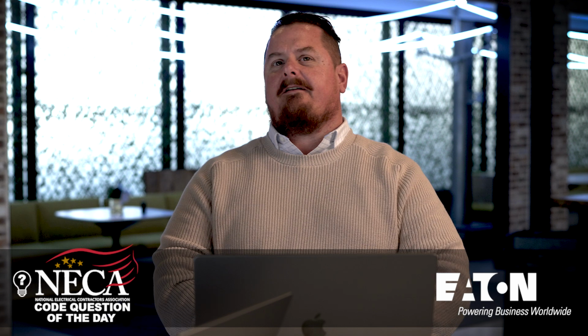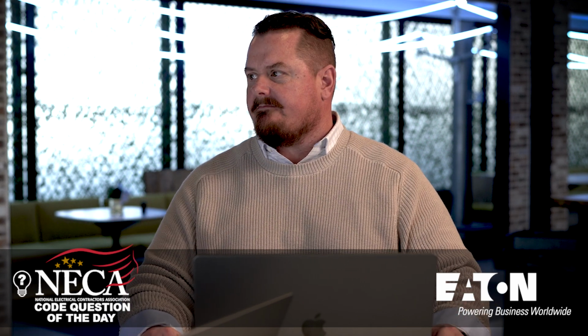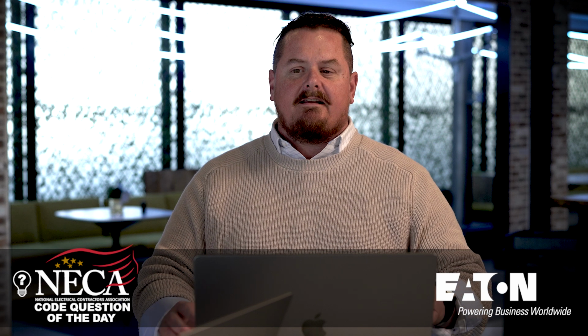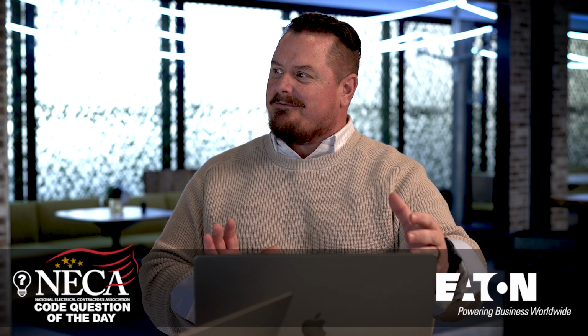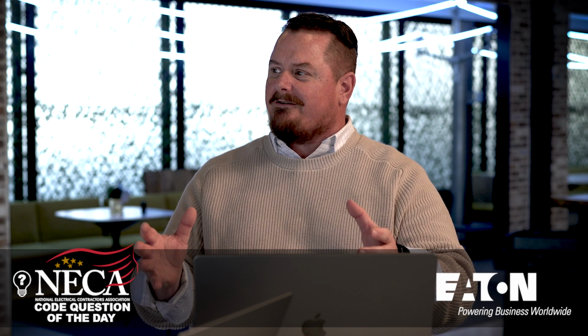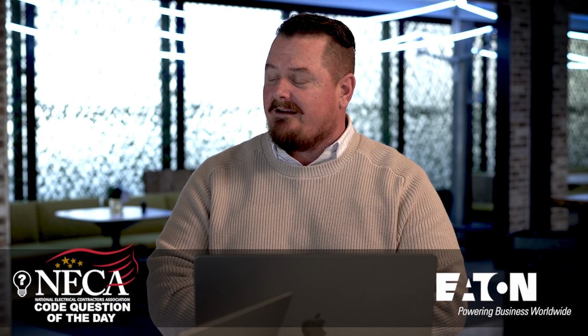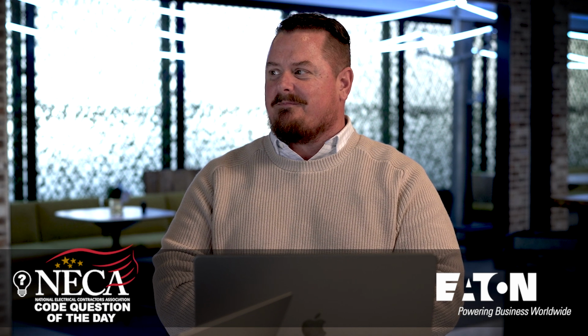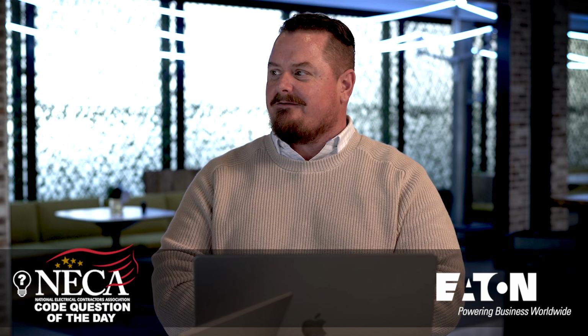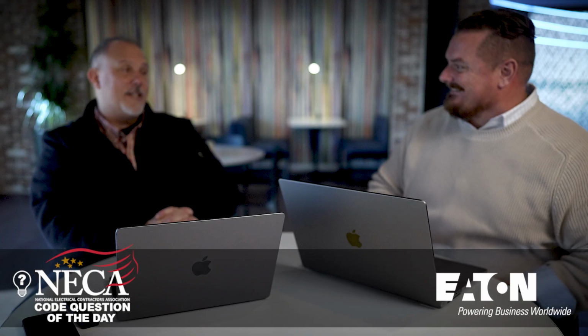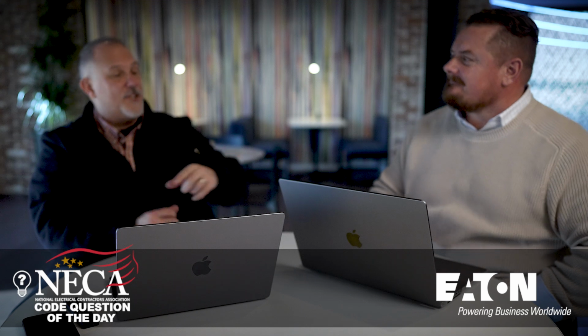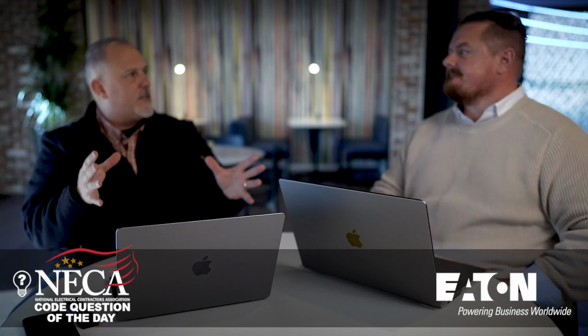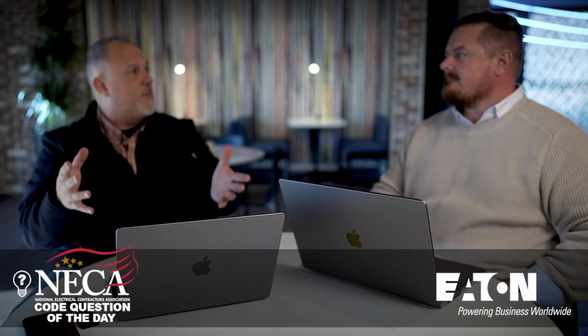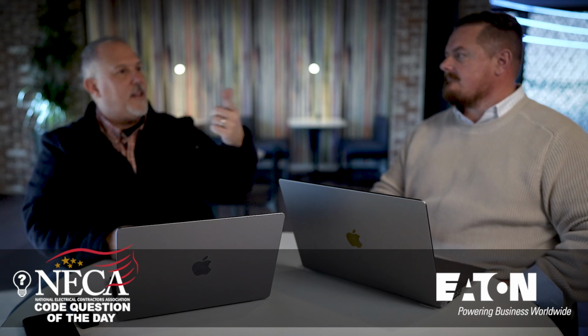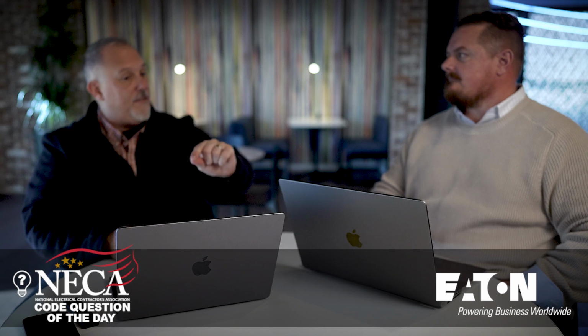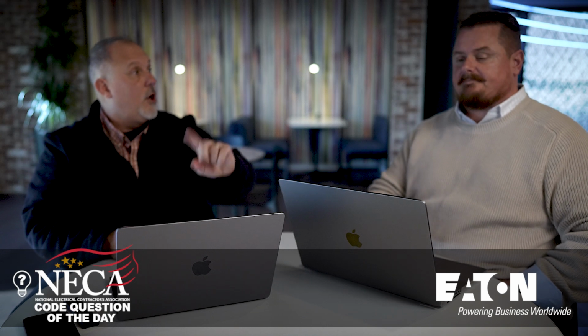If it's an industrial control panel that you built in accordance with Article 409 of the NEC, you don't have that listing element to work around, right? Sure. But if it's part of an elevator control system or a piece of HVAC equipment, and you start taking things out and replacing things, you might find yourself in a whole other world of hurt that you don't want to be involved in. Exactly, but here's what I learned in that process. I'm looking at that diagram and all the components, and I'm like, well, shoot, they can take this to 65K pretty easy. So I told them, call the manufacturer and ask if they have the ability to make these modifications in the field, or what.